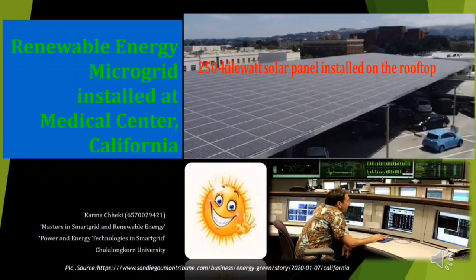The project also developed a novel microgrid controller that can island the hospital life safety emergency power branch, including emergency lighting, and provide power service during emergencies. During non-emergency periods, the controller enables the microgrid to achieve performance goals such as reducing utility energy consumption, site peak demand and utility costs, with the capability to participate in demand response.